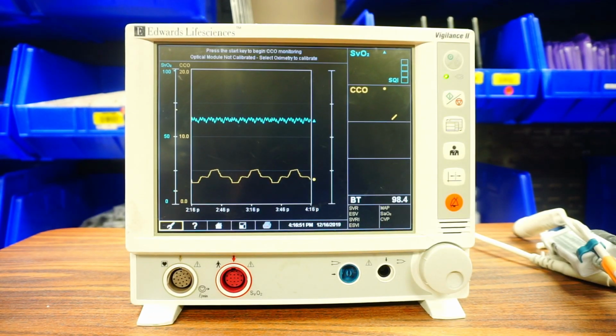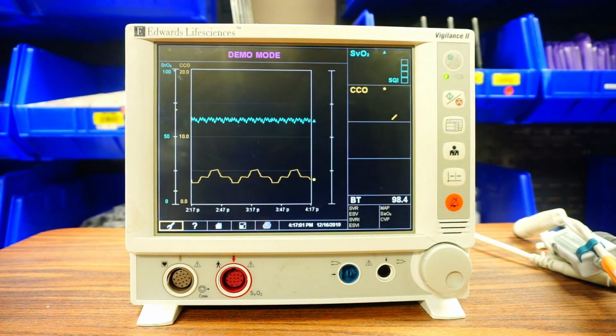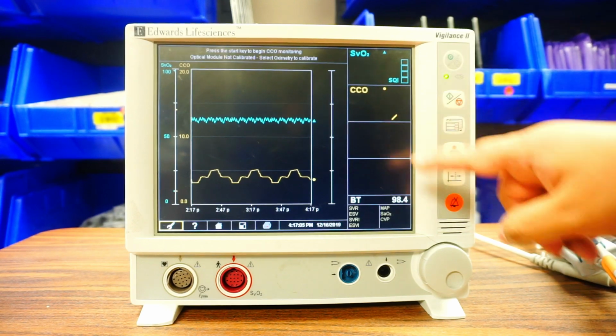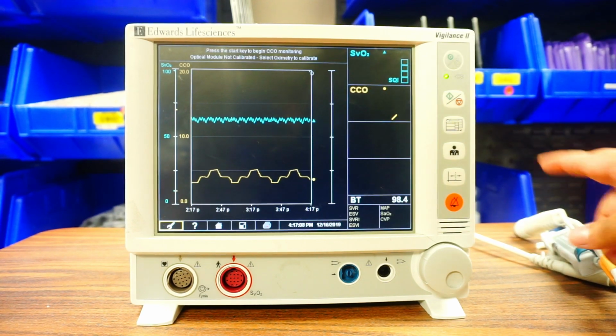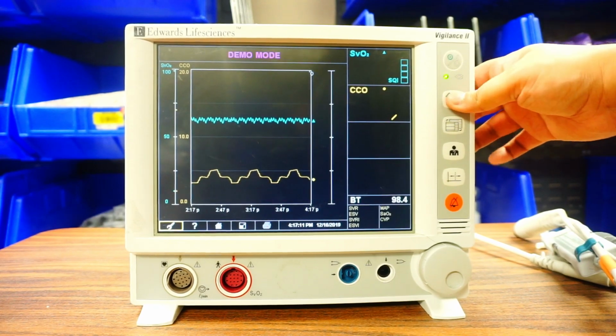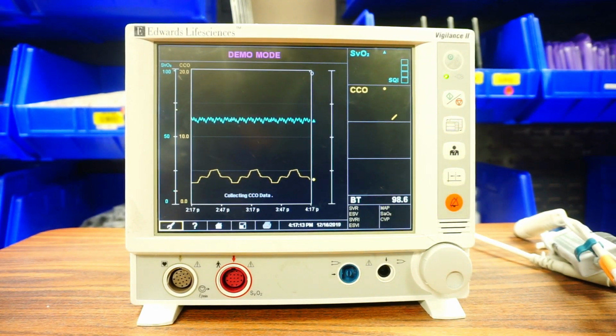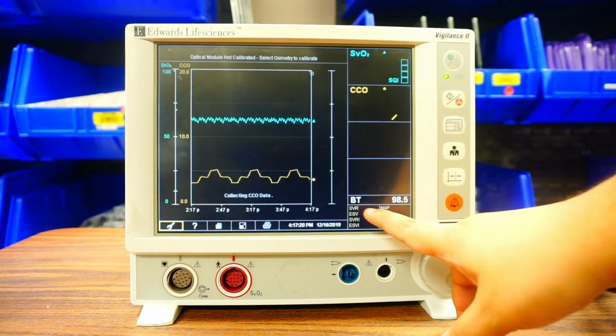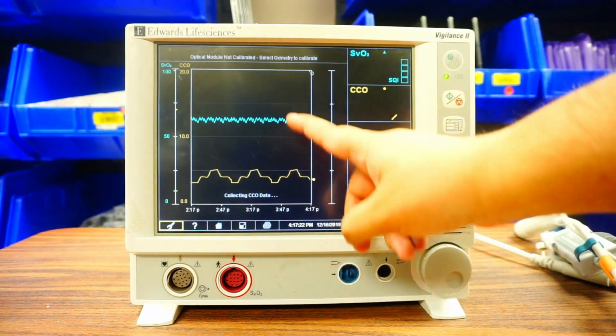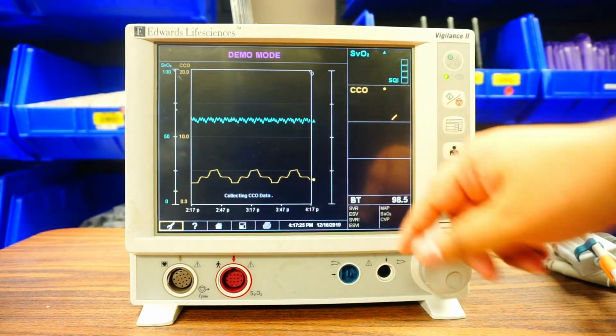Okay, so I went ahead and put the monitor in demo mode just so that we could see some numbers on here, since this Swan isn't in an actual patient right now. So to get your cardiac output running, similar to on the other machine you had your green go button, this is your green go button. So you're going to press that and then after about a minute, it is going to get your cardiac output and will calculate your cardiac index. Your core temp is going to be down here. You got your time. You're going to see your graphic trends of the patient.